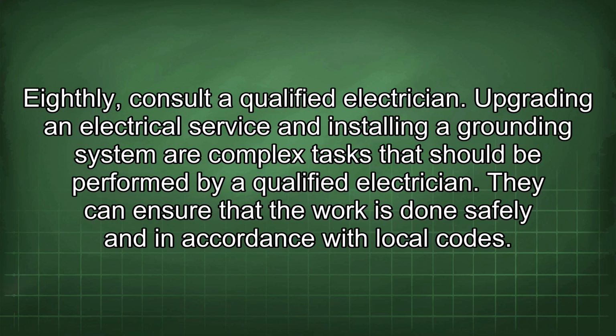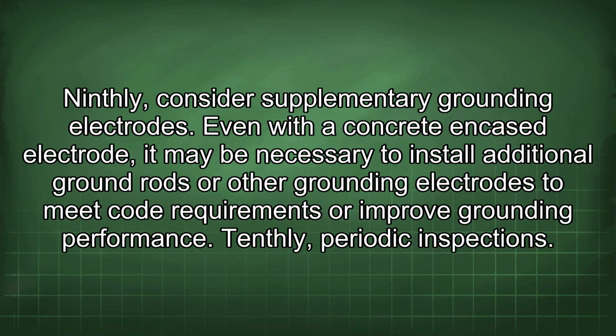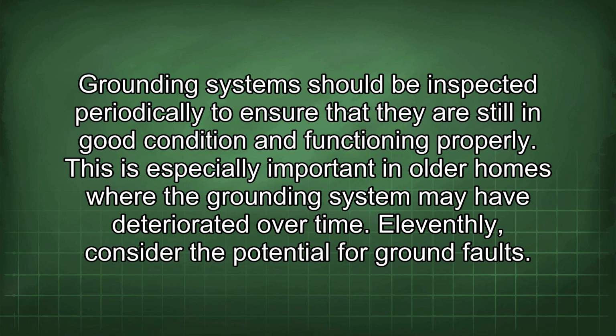Eighthly, consult a qualified electrician. Upgrading an electrical service and installing a grounding system are complex tasks that should be performed by a qualified electrician. They can ensure that the work is done safely and in accordance with local codes. Ninthly, consider supplementary grounding electrodes. Even with a concrete encased electrode, it may be necessary to install additional ground rods or other grounding electrodes to meet code requirements or improve grounding performance. Tenthly, periodic inspections. Grounding systems should be inspected periodically to ensure that they are still in good condition and functioning properly. This is especially important in older homes where the grounding system may have deteriorated over time.